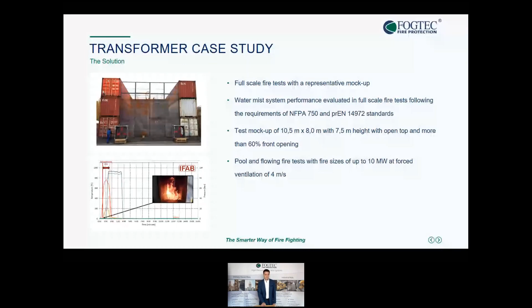At the end, the protection concept was that we have to protect the grid soil below the transformers for oil leakage or spillage, and then on the sides and top with rings we created a water mist enclosure for the entire transformer, which works well even with openings. The filling effect of the high pressure water mist was substantial enough to house the entire transformer, even with some openings, giving a satisfying effect for the whole enclosure.